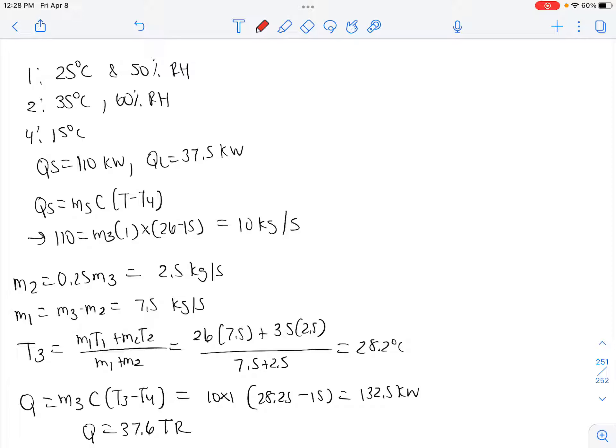Our QS is 110 kilowatts and our QL is 37.5 kilowatts. So we can set QS equal to M3 times C for air times T minus T4. So we have M3 times 1 times 26 minus 15, giving us M3 equals 10 kilograms per second.